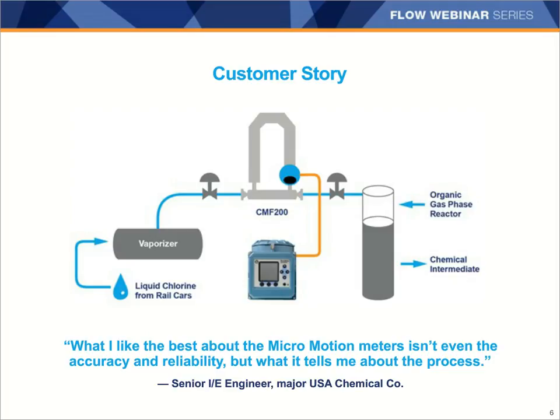Unfortunately, the differential pressure, or DP meter, that they were using wasn't accurate enough to properly control the chemistry of the reactor. At one point, the reactor actually went out of control, and it resulted in a backflow of acid through the chlorine gas feed system. There was absolutely no indication that this had happened, and a fire resulted. Unfortunately, the fire actually caused a fatality. So as you can imagine, this immediately drove the customer to carefully consider different alternative measuring technologies to help reduce risk and try to prevent something like this from ever happening again.